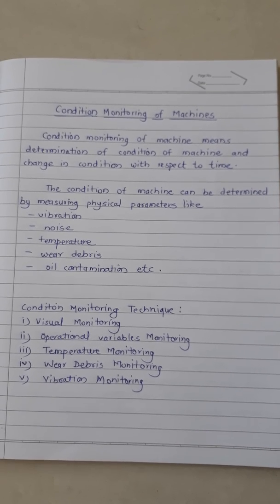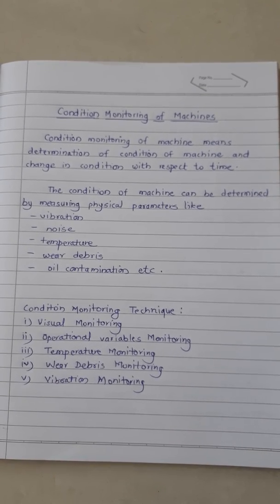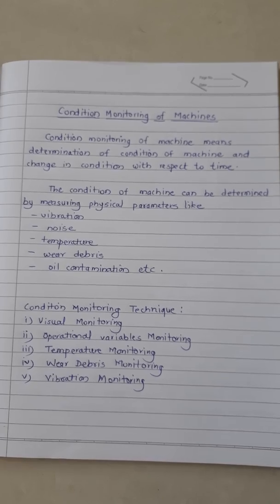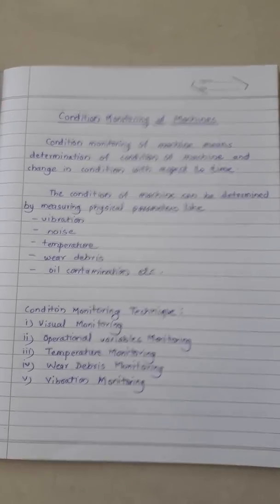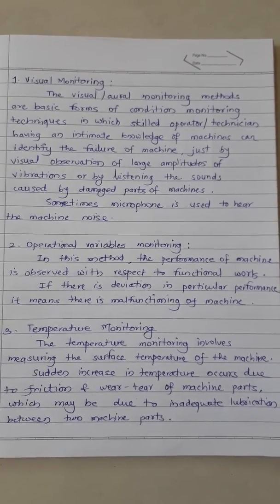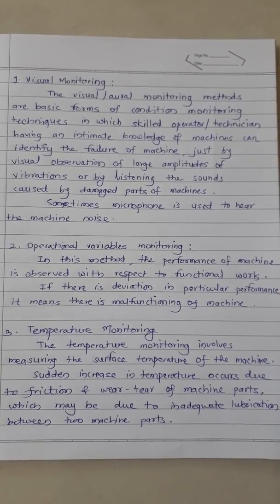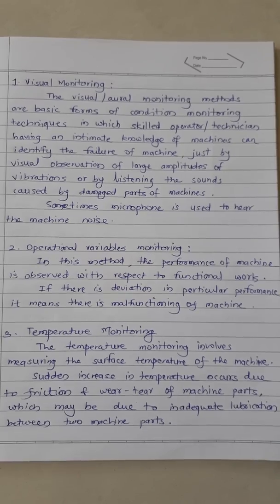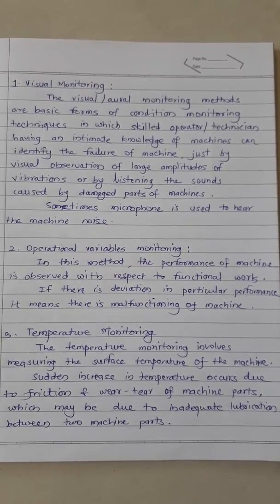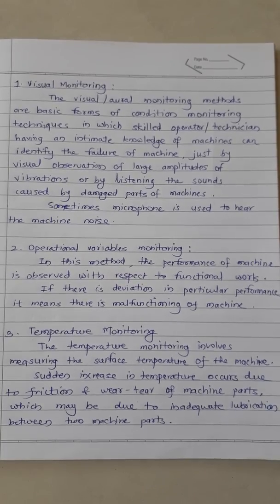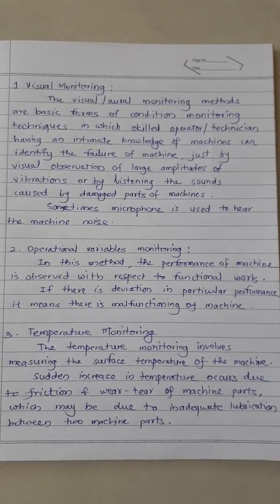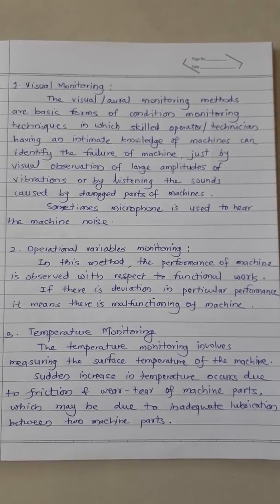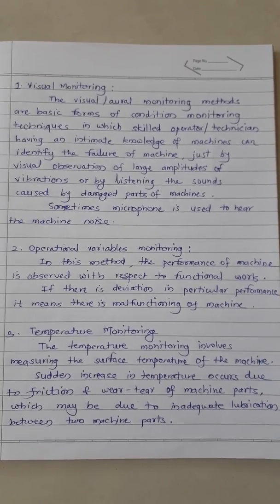There are some techniques for condition monitoring. First is visual monitoring. Second is operational variables monitoring. Third is temperature monitoring. Fourth is wear debris monitoring. And fifth is vibration monitoring. Visual monitoring: the visual or aural monitoring methods are basic forms of condition monitoring techniques in which a skilled operator or technician having intimate knowledge of machines can identify the failure of a machine just by visual observation of large amplitude vibrations or by listening to sounds caused by damaged parts. Sometimes microphones are used to hear the machine noise.